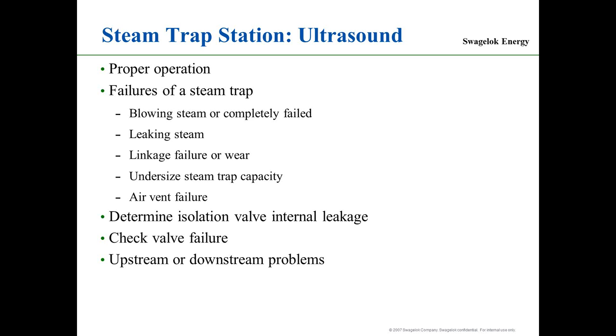It's not that difficult. Steam trap station to ultrasound proper operation: what I can find is whether the steam trap is working correctly, period. Very simple. Failures, blowing steam or completely failed, are very simple to pick up. Leaking steam, I can find that, not a problem. And with experience, you can determine the degree of leakage of steam. Linkage failure or wear. Again, the ultrasound gives you the ability to climb inside the steam trap and see what's going on.